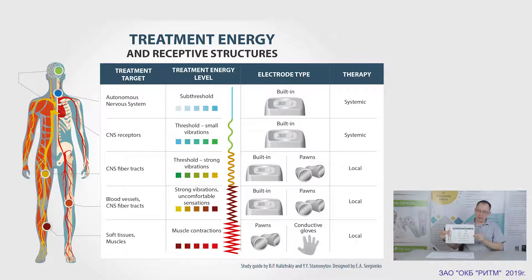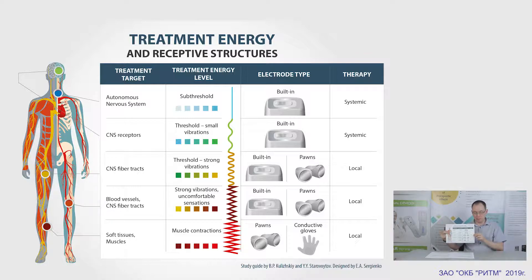The upper threshold level influences the paths of the central nervous system and can be used for conducting-type myostimulation, the treatment of the nervous roots and plexus, as well as for local anti-edemic, anti-inflammatory, and anti-pain therapy. At this level, we can use both built-in and external electrodes.